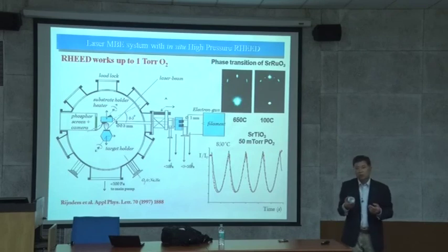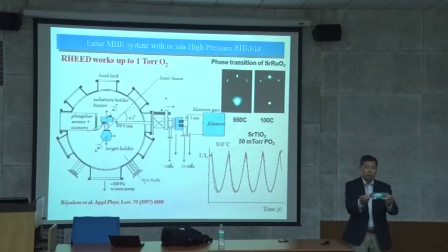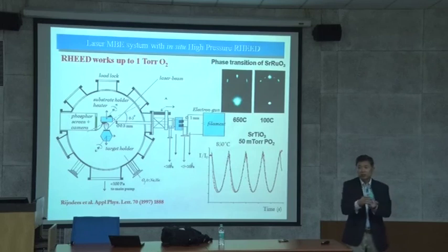How do you overcome this problem? Most of the laser comes this way, and I think this is a trick that we have learned. You rotate this beam, because the excimer laser has a rectangular beam profile, and different lasers have different ones. So you rotate this beam from this orientation to this. Then your beam is coming this way, and you are less likely to have over focus and under focus.